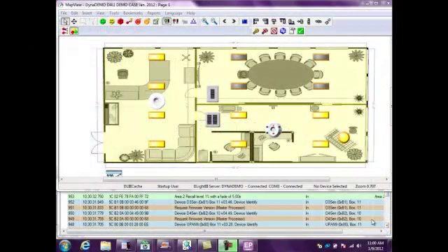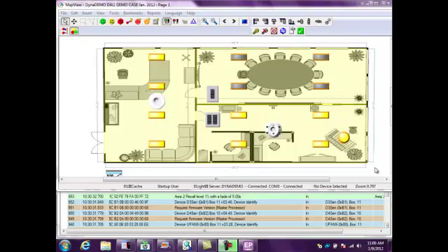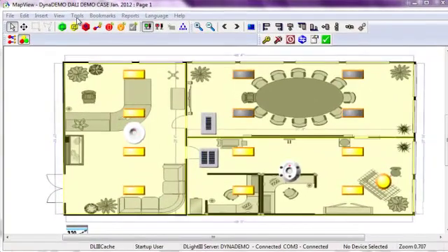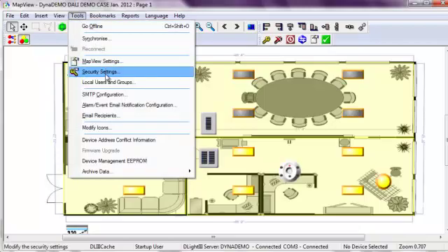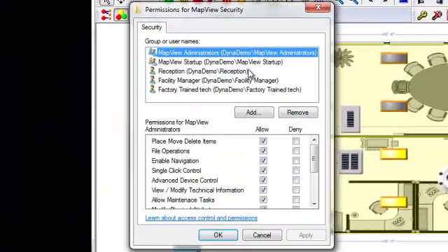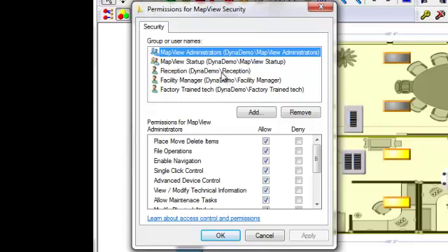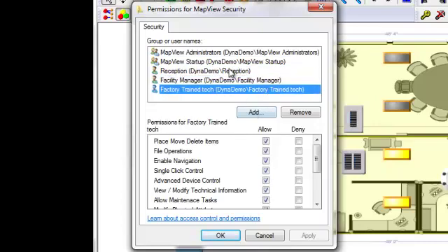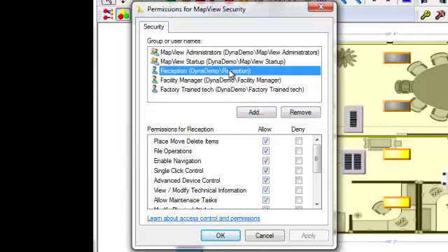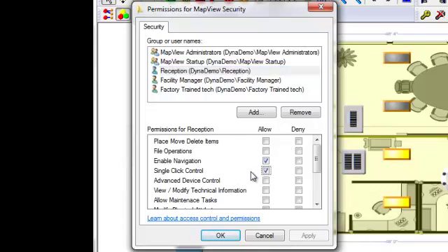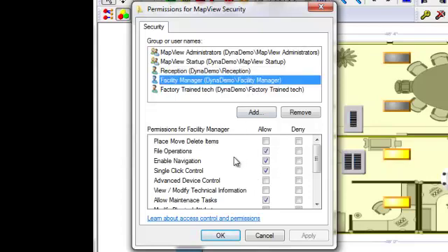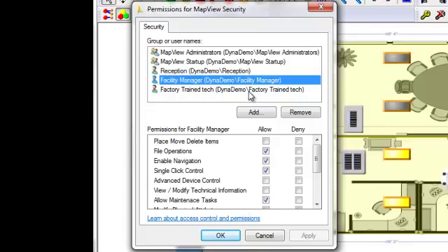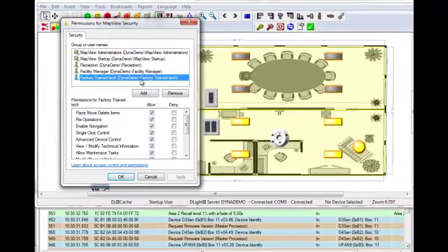For most facilities, you're going to need different access for different features for different people. And the way you can set that up is through tools, security settings. And as you can see here, we have some different people named already. We have our receptionist, our facility manager, and our trained tech. Our receptionist will have access to file navigation so she can flip between pages. But she also has single-click controls so she can turn an area on or off by pressing the keypad. Now, we step into the facility manager. And he not only has that single-click control and enabled navigation, but he also has file operations and ability to allow maintenance tasks. And then you can step up to, say, the factory trained tech, who has access to all the features at all times.